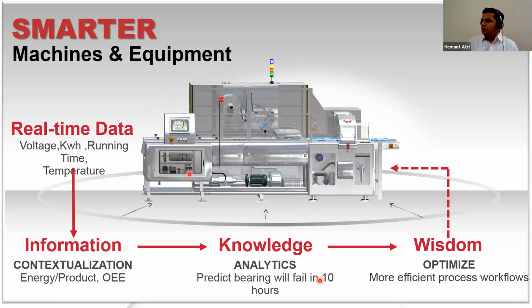There will be certain small drift that starts appearing, certain noise or vibrations that start going up, the motor load currents will also start going up, and the rate of change will be very slow and steady. But over a period of time, as that builds up, it will further deteriorate, and on one fine day it will fail.